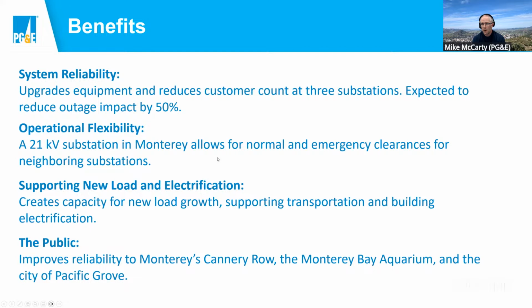So benefits for this project, just to keep going into those details. We're reducing the customer count on the 3 substations in the area. That is really where the benefit to reliability comes from. And I'll go into a little bit more detail on that on the next slide. And we're also upgrading our equipment and bringing it into the new standards. With the conversion, this allows on the operational flexibility side, it gives us more capacity to do routine maintenance because we now have a new 21 kilovolt source in the area.